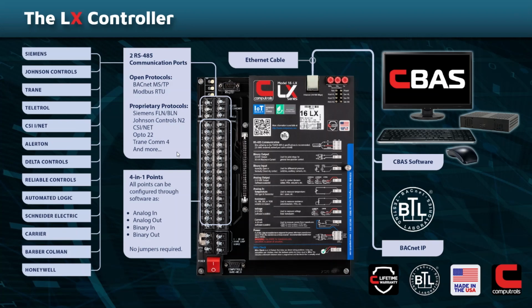Let's take a closer look at the LX. This is the 16-point model. Notable at the top, you can see two RS-485 ports, which is how we communicate via twisted pair daisy chain to third-party protocols, as shown in that list on the left. Those ports are independent, so any port on any LX can accommodate any protocol, giving you the ultimate in flexibility and expandability going forward.